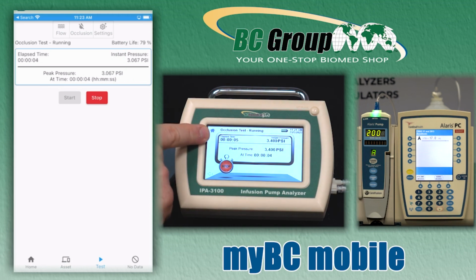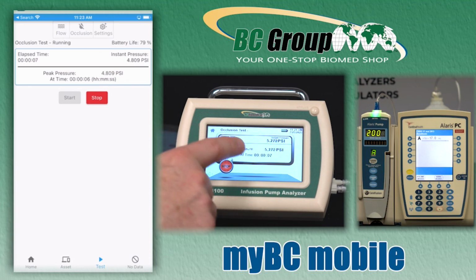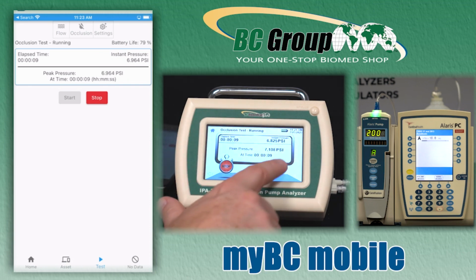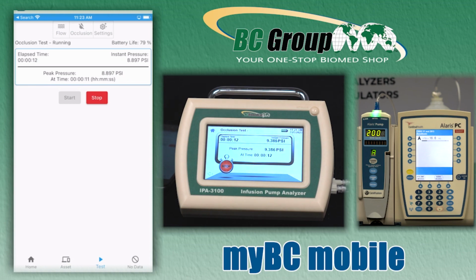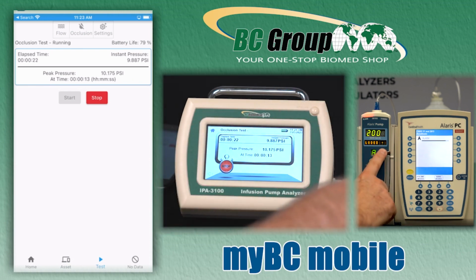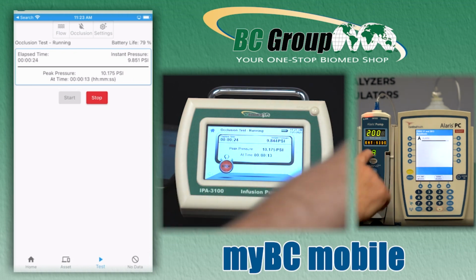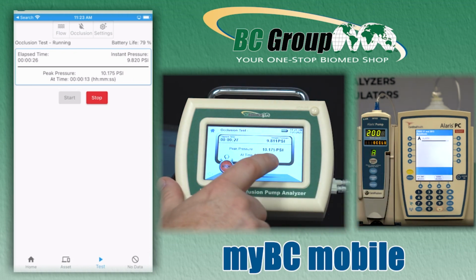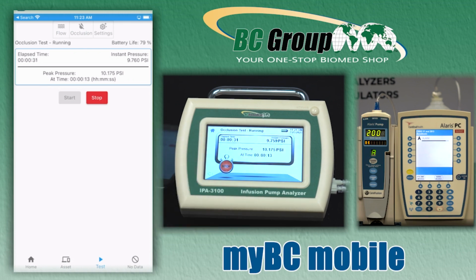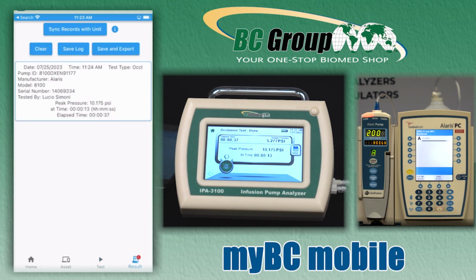It started measuring. It started counting time. And it's monitoring the pressure that's coming in, and it's recording the peak pressure. And it's telling us when that occurred. And we can see on myBC Mobile, it's showing the same information on the screen here. So we got an occlusion. The pump detected occlusion, and it stopped pumping. So we can see when that occurred. That occurred at 13 seconds, and the pressure was 10.175 psi. Now at this point, we can press stop to finish that test.